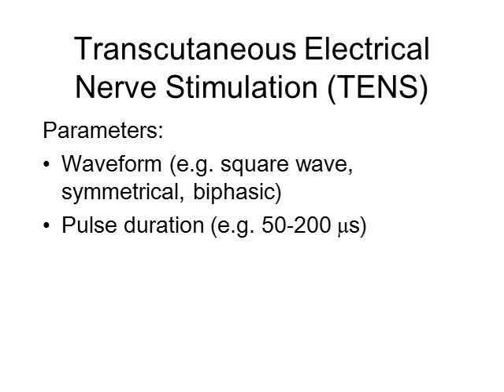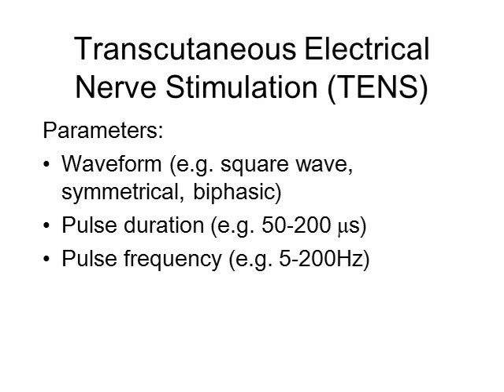Pulse frequency, or pulse rate, is the number of pulses per second, and on most devices is variable between 5 and 200 pulses per second. Increasing the number of pulses stimulates nerves more easily, typified by the strength frequency curve.